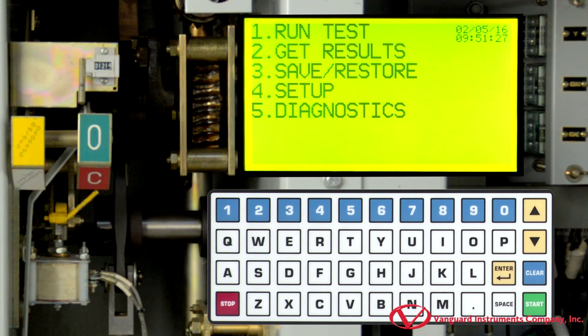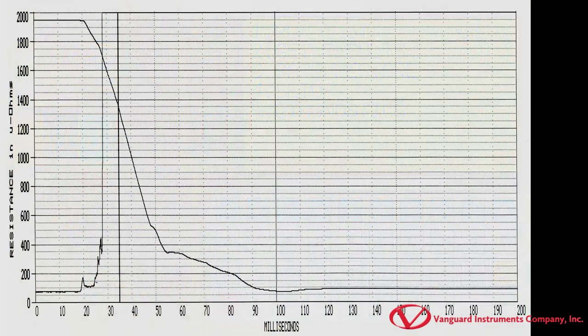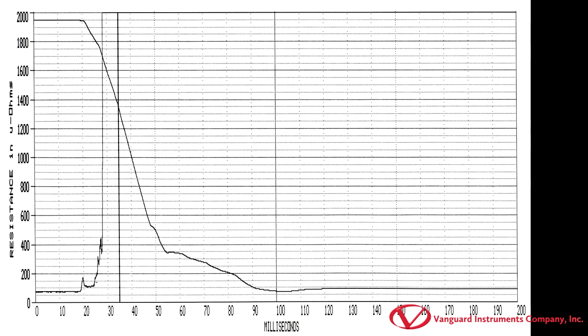Next, we will take a closer look at the test results. Here is a sample printout of the dynamic resistance test results from the CT8000S3's thermal printer. The x-axis represents time in milliseconds, while the y-axis represents resistance in micro-ohms.